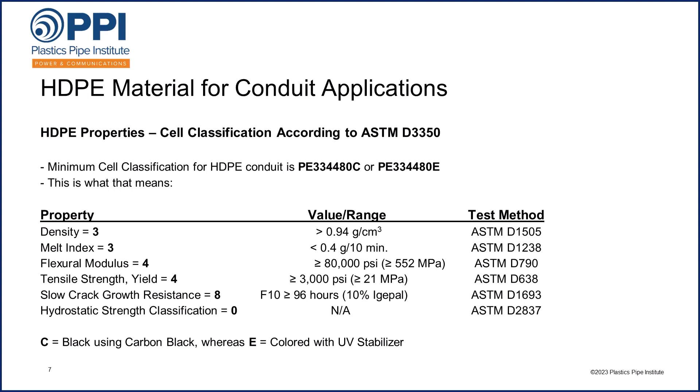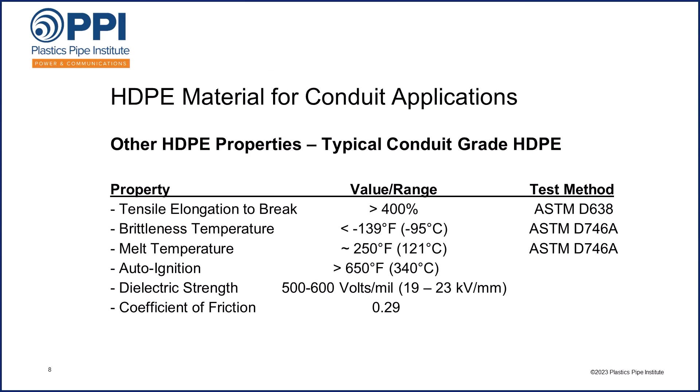There are also other properties which are not part of the cell classification but which are still interesting to know for conduit applications. For instance, when it comes to typical elongation at break, the requirement is for over 400%. If you tried to stretch HDPE conduit, it would elongate at least 400% before it would break. Its brittleness temperature, otherwise known as glass transition temperature where it actually becomes brittle, is below minus 139 degrees Fahrenheit. Its melting temperature is around 250 degrees Fahrenheit. Its auto-ignition temperature is over 650 degrees Fahrenheit. It has a dielectric strength value applicable to some conduit applications of 500 to 600 volts per mil, and its coefficient of friction is approximately 0.29.